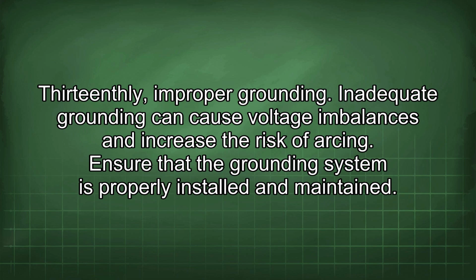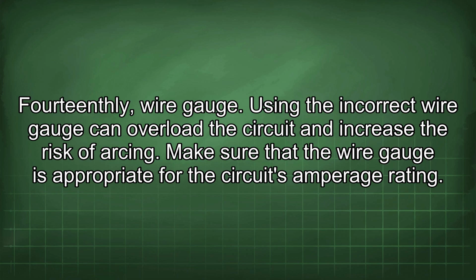Thirteenthly, improper grounding. Inadequate grounding can cause voltage imbalances and increase the risk of arcing. Ensure that the grounding system is properly installed and maintained. Fourteenthly, wire gauge. Using the incorrect wire gauge can overload the circuit and increase the risk of arcing. Make sure that the wire gauge is appropriate for the circuit's amperage rating.